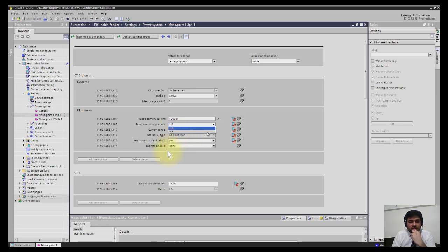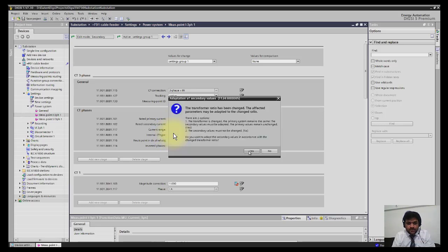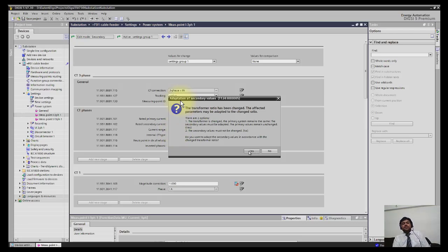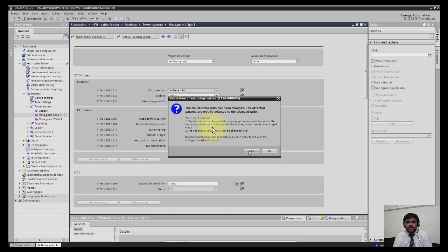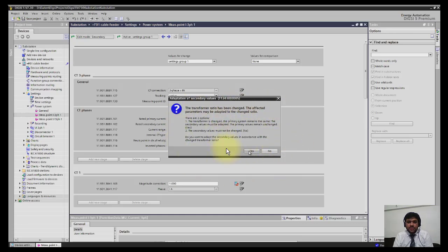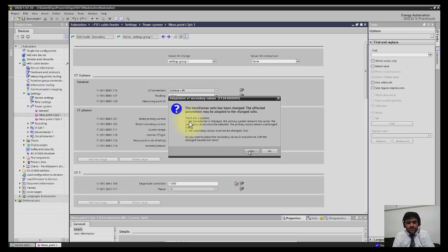Here it is very flexible—just a single click and you can select your required secondary current. DIGSI 5 has another excellent feature: once you change the CT ratio, DIGSI 5 will change your settings automatically as per the new ratio. This is one of the excellent features that I like in DIGSI 5.